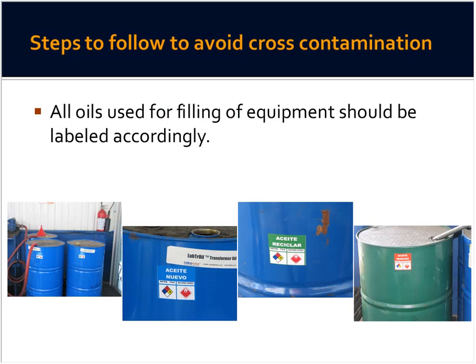The second label says recyclable oil. This is oil that is PCB free, has been taken out of other transformers, and has probably gone through a regenerating process, so it can be used for refilling clean transformers. The third drum is labeled waste oil, meaning the oil has been proven to be contaminated and cannot be used anymore.